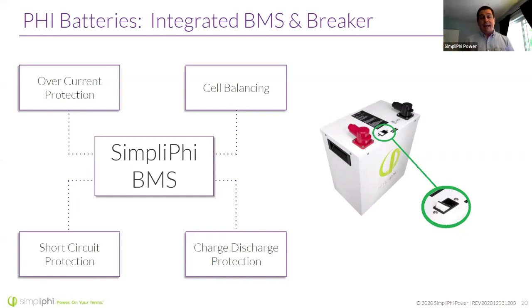Another thing that every one of our batteries has is a breaker, which is a great feature in my opinion, for safety, transportation, installation, and troubleshooting. If you're using your torque wrench to attach battery cables to these terminals and the battery is in the off position, you're in a safe place. If you're doing connections on a battery that's hot, you really have to make sure you don't touch that torque wrench to both terminals, that could be a catastrophic and dangerous event. So by introducing a battery breaker on every unit, we provide the maximum level of safety for the user.